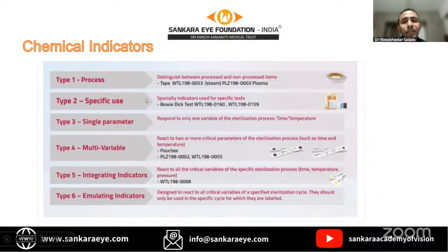And type 2 is for specific use. Commonly we use the Bowie-Dick test, which is a type 2 indicator, to confirm whether the vacuum is completely created and the air is completely removed. So for each purpose, different types of indicators are available.